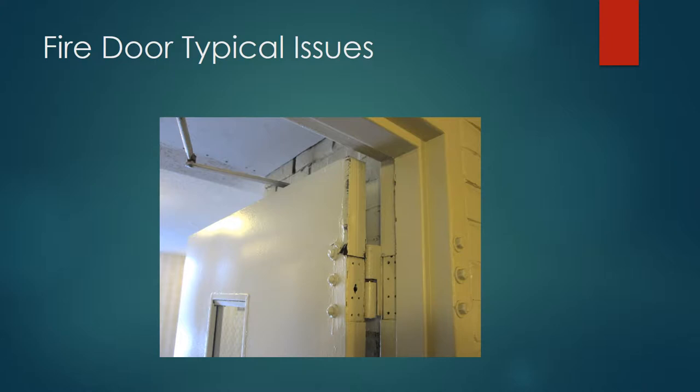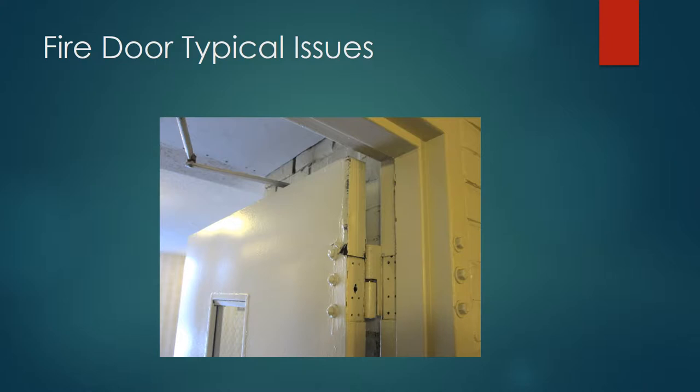Something's odd about this next door. If you look at the hinge assembly and the modifications made to the door, you have to wonder if that's a rated modification — and it probably is not. There's also a label that says 'fire — keep door shut,' and then they locked it. This may not be a rated door; this could be a partition or a hazardous space.